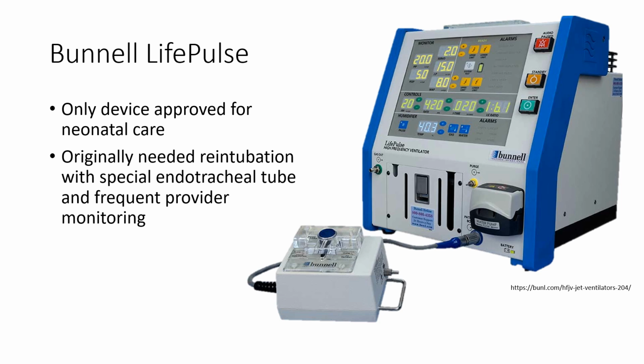The high-frequency jet ventilator is a microprocessor-controlled, pressure-limited time-cycled mode of ventilation that utilizes pulses of gas through an injector to achieve ventilation. The Bunnell LifePulse is the only device on the market for use in neonatal patients. The 2 models of the LifePulse are the older 203 model and the more recent 204 model.